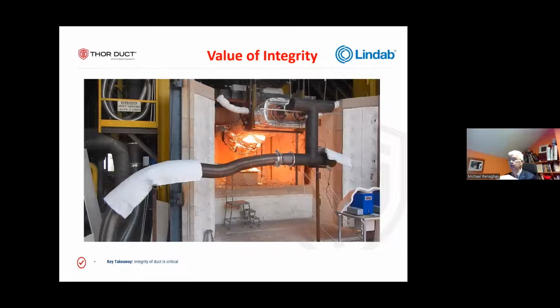So the forces disappear. But at this point, it's no longer being contained by the brackets. So this is a bad design. And of course, if you put an insulation that's very good on a duct, you need to test the two together to validate that the two perform together. Because clearly, good insulation can kill a duct. To have a good result, you need a good insulation with a very strong duct, or a very cleverly designed and built duct. Okay, so that's what you need to do.